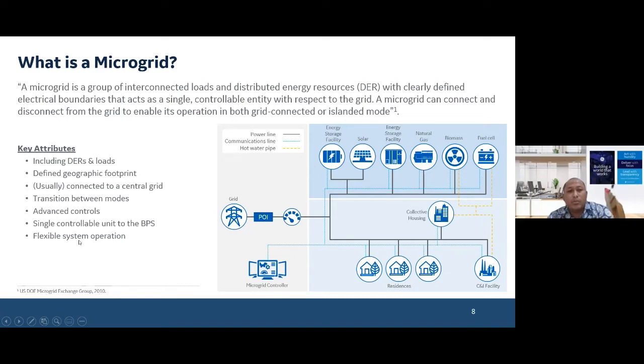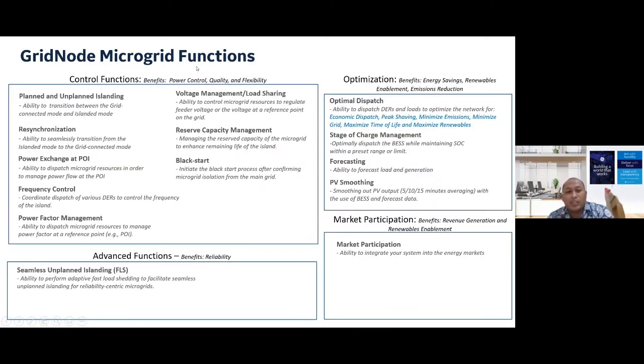We can see here also what the function of a microgrid is. The microgrid itself has a few functions, such as a control function, an optimization function, an advanced function, and also market participation. Inside of this control function, there are many functions, such as planned and unplanned islanding, which is the ability of the system to transition between the grid connected mode and island mode. And then the resynchronization, which is the ability to seamlessly transition from the island mode to the grid connected mode. And many more functions under this control function that the customer can apply when they are applying this microgrid system in their existing system.